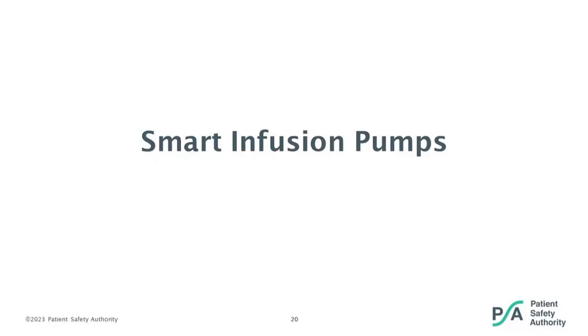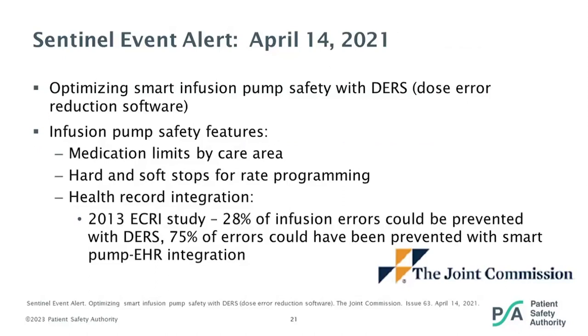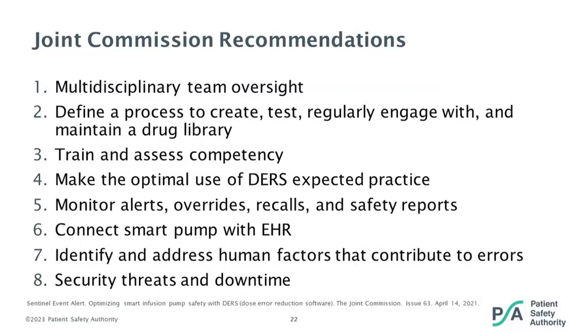Next, we'll take a look at smart infusion pumps. Smart infusion pump technology with dose error reduction software has improved safe administration of IV medications over the past 20 years. In 2021, the Joint Commission published a Sentinel Event Alert regarding optimization of this technology. Important safety features include medication limits built into the drug library and both hard stop and soft stop limits for rate programming with guardrails. A 2013 ECRI study identified that while 28% of infusion errors could be prevented with dose error reduction software, 75% would be prevented with integration between the electronic health record and the smart pump.